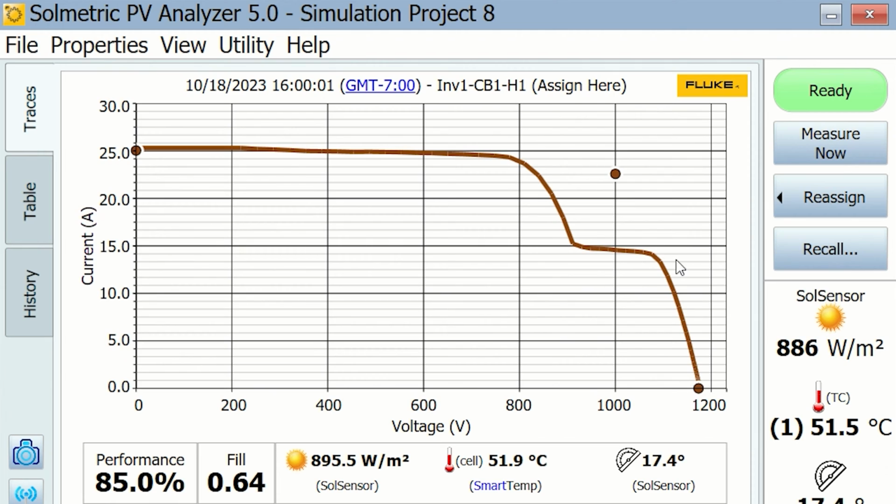And indeed, something would be wrong here. The best way to put this is an example of what a faulty panel or a faulty string might indicate. A full chunk of this fill area is missing. The quickest way to look, and probably the best troubleshooting step after this, would be to go out with a thermal imager and look for a panel with an anomaly on it. But this is very indicative of a bad panel.